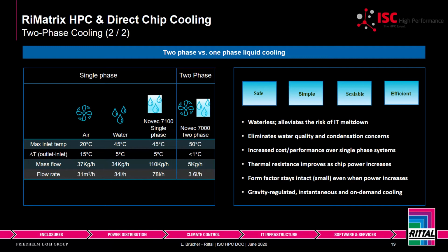In this table on the left side of the screen, we're comparing how to cool with single phase with air, single phase with water cooling, single phase also with Novec, and two-phase cooling also with Novec. If you look at the inlet temperatures, with Novec we have a temperature of 50 degrees, which is pretty high, allowing free cooling. If you go all the way to air, with 20 degrees, you cannot operate the full year with free cooling. So you will need additional equipment and CRAC, and not only capex, but also operational expense through the whole year, so you own this equipment.